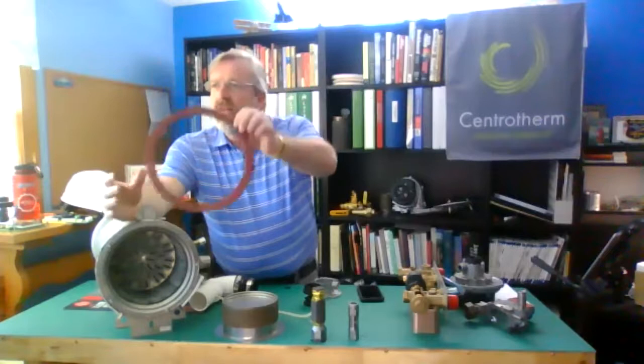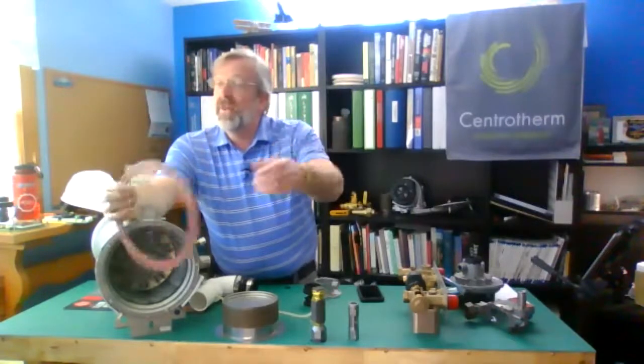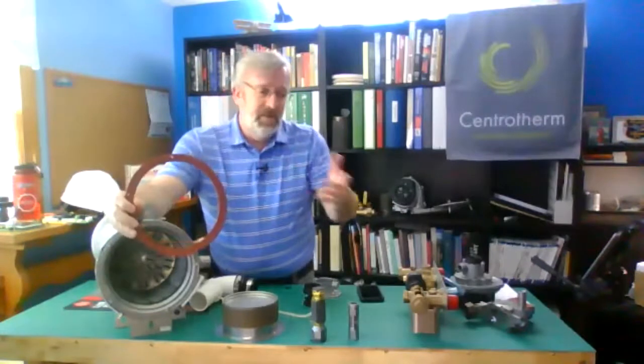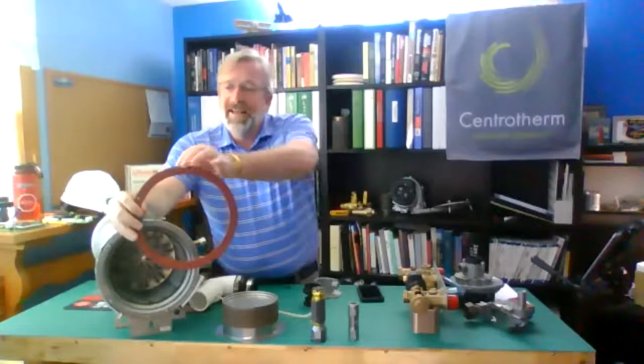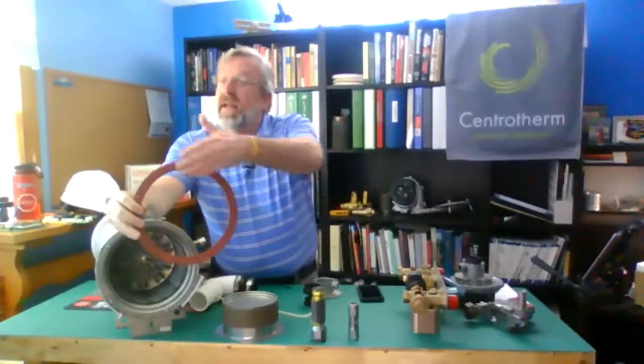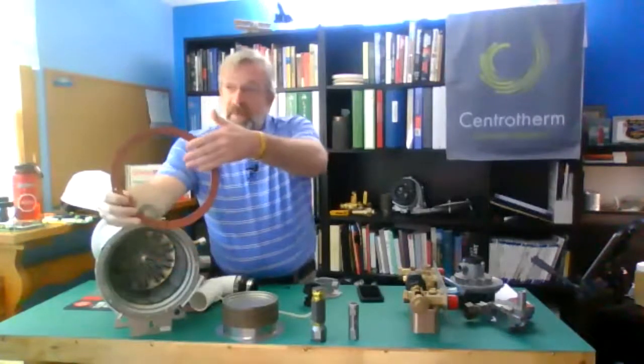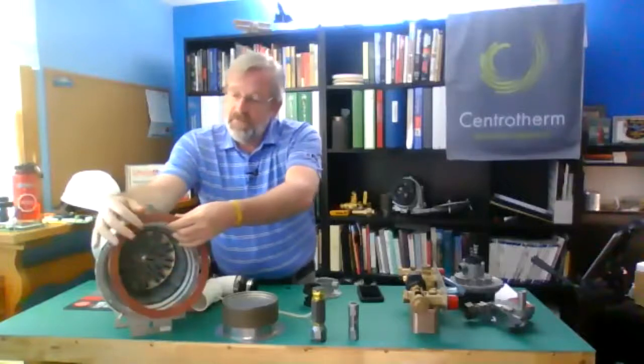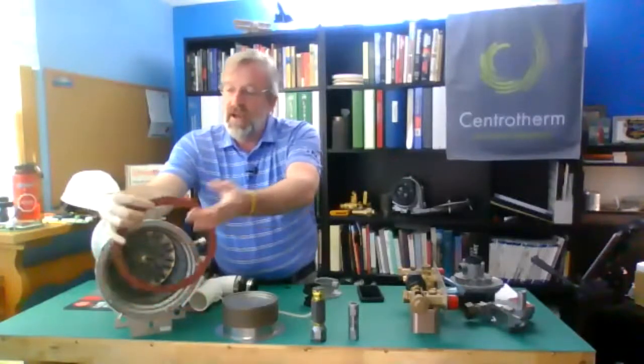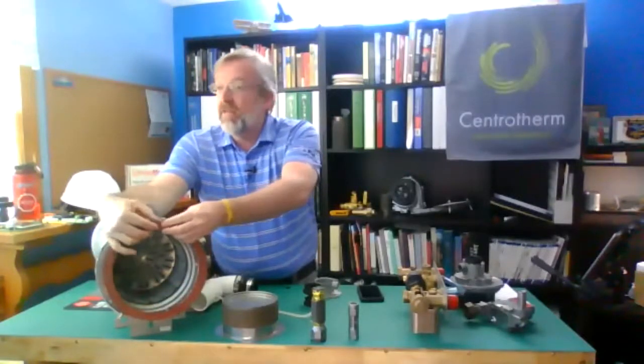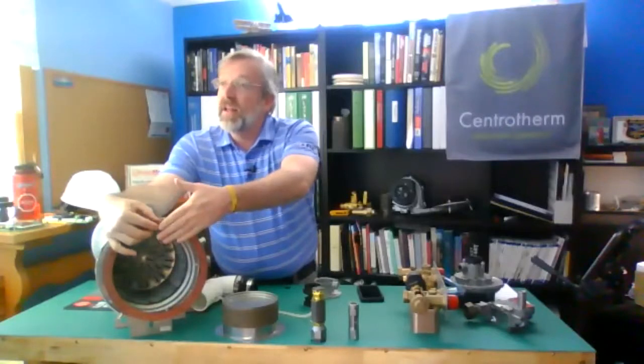Majority of the time, you'll be able to reuse this gasket. The exception to that could be if the boiler's been in there for four, five years. They don't use an outdoor reset. They run it hot. They cycle it on all the time. And this could get real sticky. But again, that's a good spot to get in there with maybe a putty knife and separate it. A lot of times, in fact in this one, it did stay right here, and it's going to stay on the heat exchanger.